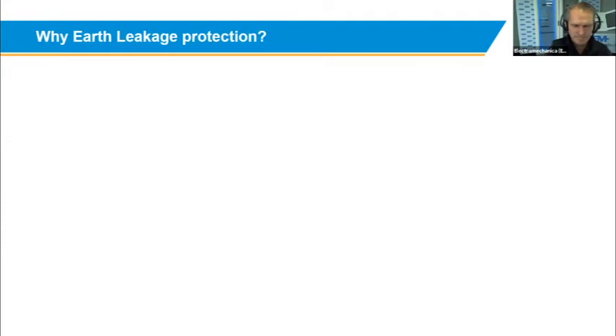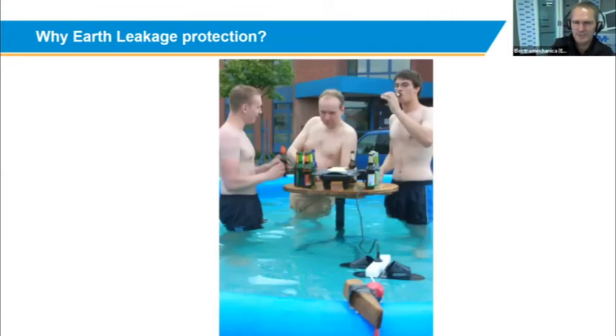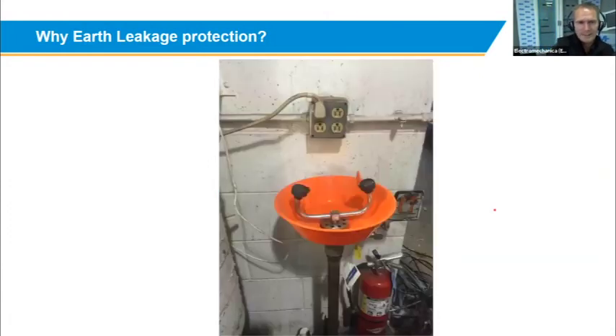Okay, then why earth leakage protection? As I said earlier, if the installation was done according to all the required regulations, there's not supposed to be any leakage to earth. So the first reason would be because of alcohol and a little bit of stupidity. You can see these guys are also standing dead quiet, and you can see they're looking at what is going on here. So yeah, alcohol you can call the one. This one is in a factory where it's an eye wash basin. So you actually need to drop your head down to wash your eyes through the water that will spray out there, and your head is touching the point there. Very clever, very clever. Good engineering.